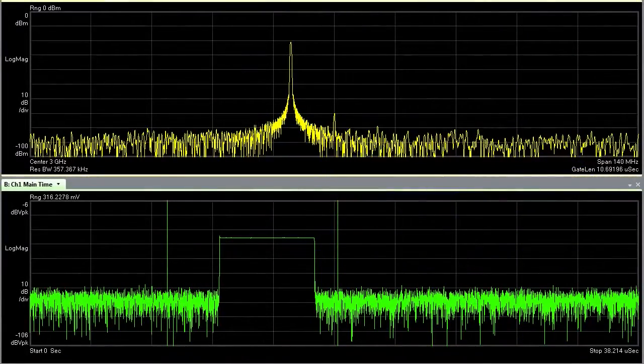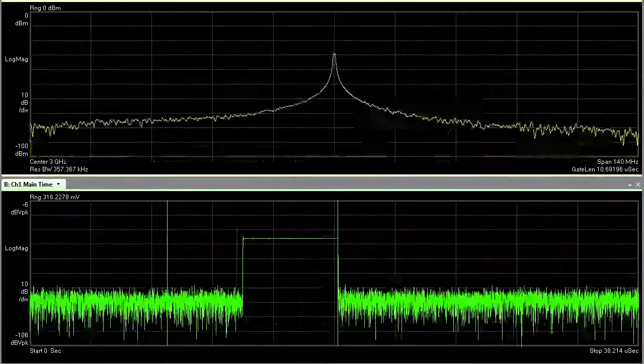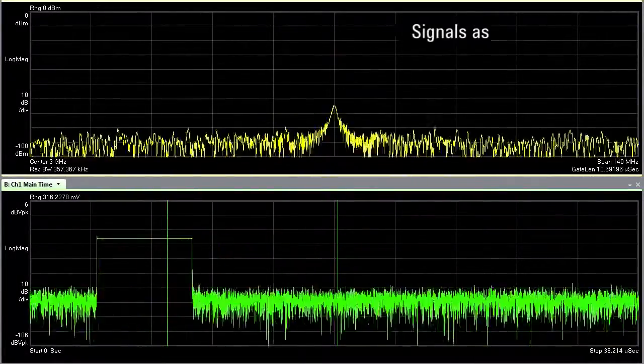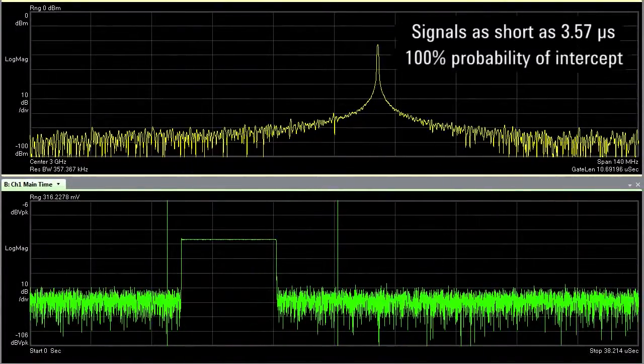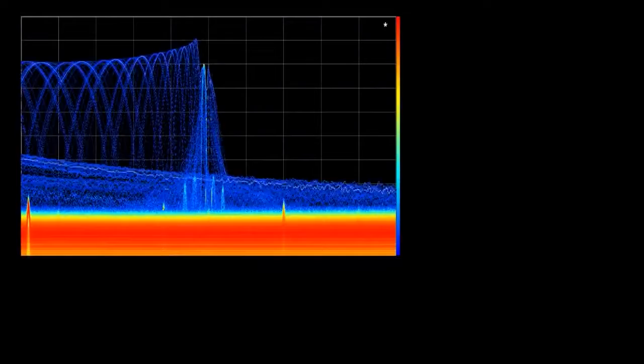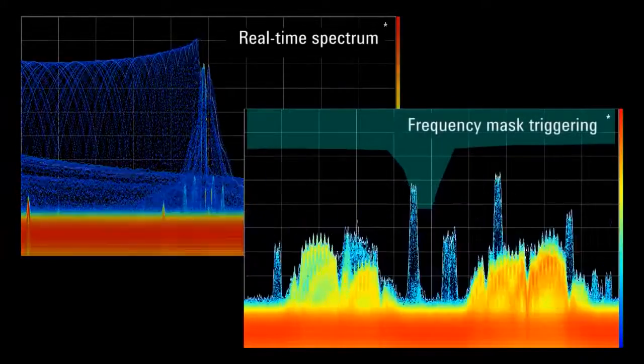A fundamental task for a real-time analyzer is to make sure you don't miss any signal. In the PXA, signals as short as 3.6 microseconds can be detected with 100% probability of intercept. All this performance is available for both real-time spectrum measurements and frequency mask triggering.